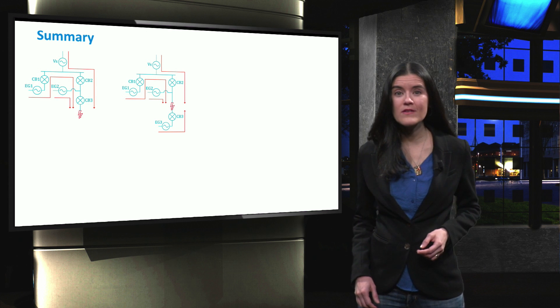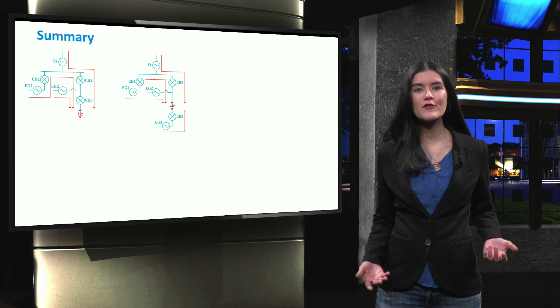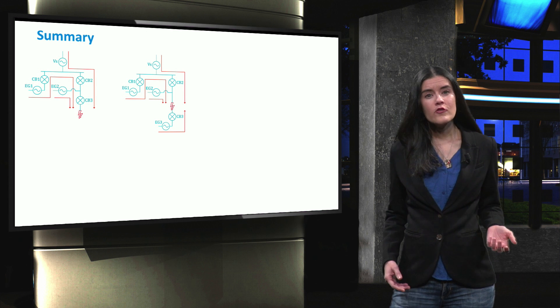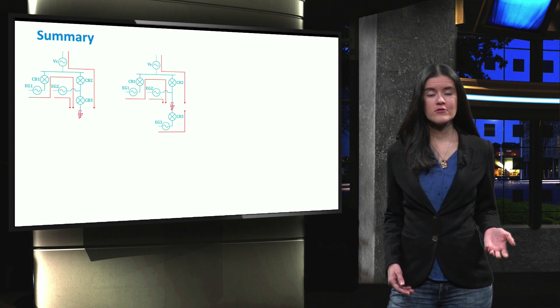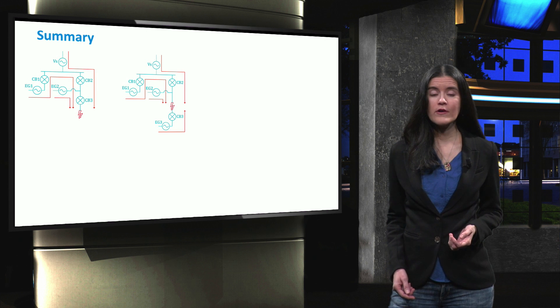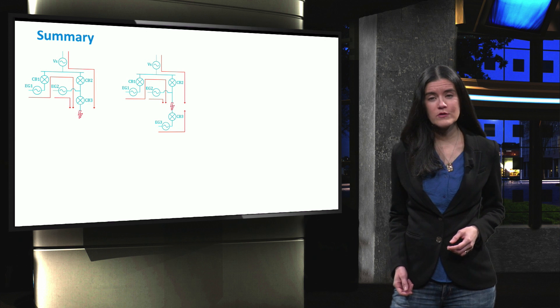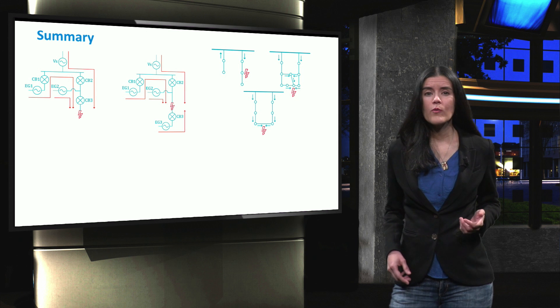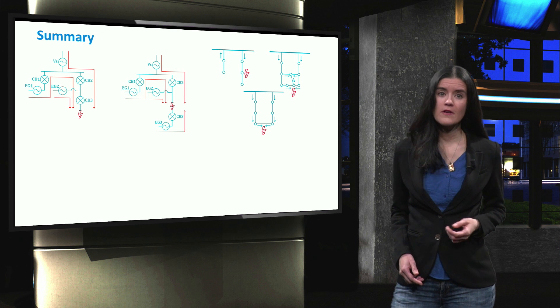In summary, we saw that the main protection challenges in microgrid consist of mal-operation or false-tripping of circuit breakers, due to lack of overcurrent protection coordination and change in current direction, change in the short circuit's current level between the islanded and grid-connected modes of operation, and changing network configurations.